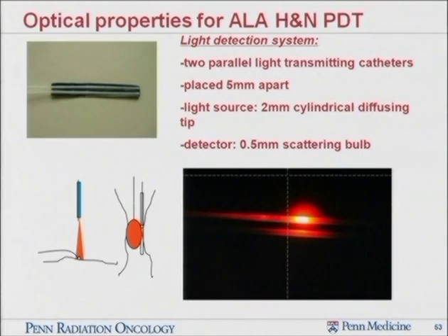So we introduce a point source and a detector into the catheter, stepping the detector to different locations, and also stepping the linear source, using the so-called point source method. The only difference is that now you have a semi-infinite geometry rather than an infinite geometry. There's also one complication: in the mouth there is lots of scattering from all the way around, which is why we introduced this black bag, to block it all out so that you have a point source. This is what it looks like at the bottom.